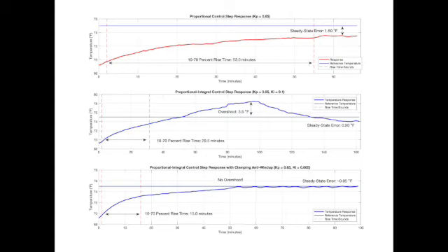Yeah, and on this plot, you can see our results. So first, with the proportional control, you can see it wasn't bad, but we still had a steady state error of 1.5 degrees Fahrenheit and a rise time, which is very long at 53 minutes. We can do better. We're trying to beat the competition here, and right now we're kind of matching it in steady state error and lagging behind in rise time.